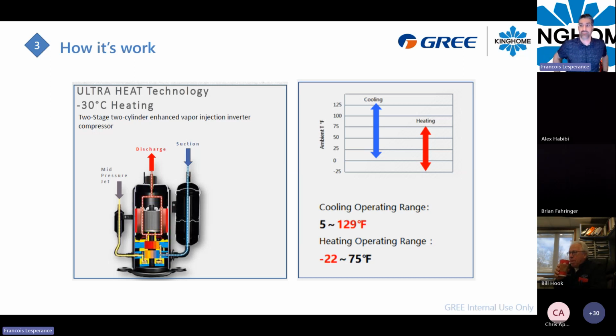Well, I haven't tested the new refrigerant yet. I will this summer. R32 or R454B will be slightly under the pressure we are seeing right now with R410A. So for the same temperature, the pressure will be reduced just a little bit. So there's no big change between what we see now with the R410A and what we will see with the R454B. It will be about the same pressure.